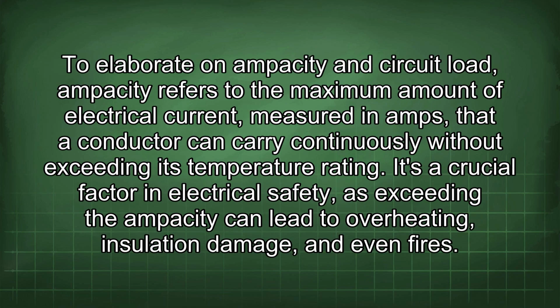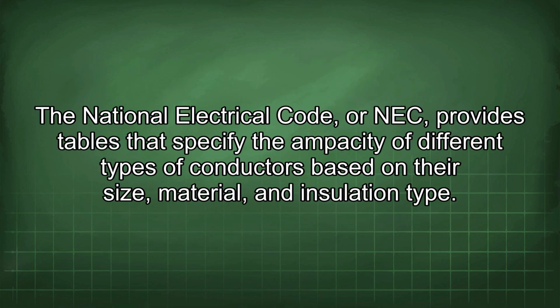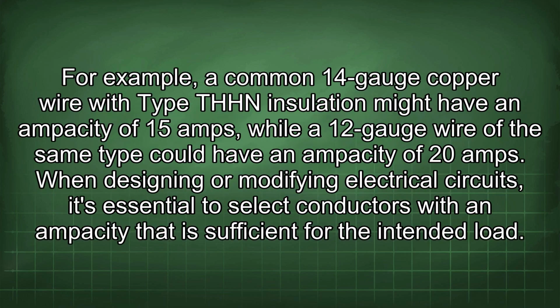To elaborate on ampacity and circuit load, ampacity refers to the maximum amount of electrical current, measured in amps, that a conductor can carry continuously without exceeding its temperature rating. It's a crucial factor in electrical safety, as exceeding the ampacity can lead to overheating, insulation damage, and even fires. The National Electrical Code, or NEC, provides tables that specify the ampacity of different types of conductors based on their size, material, and insulation type. For example, a common 14-gauge copper wire with type THHN insulation might have an ampacity of 15 amps, while a 12-gauge wire of the same type could have an ampacity of 20 amps.